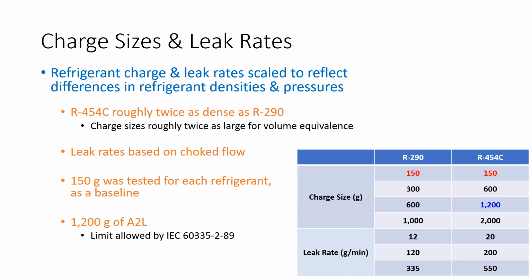Now, there are a couple of items that I've highlighted in the table that I want to point out. We also tested 150 grams for each refrigerant, as this is the baseline or maximum that is currently allowed in several safety standards for flammable refrigerants. And I've also highlighted the 1.2 kilograms for R454C that was tested, as this is the limit currently allowed by the International IEC 60335-2-89 standard, and we wanted to make sure that we covered that point. Next slide, please.